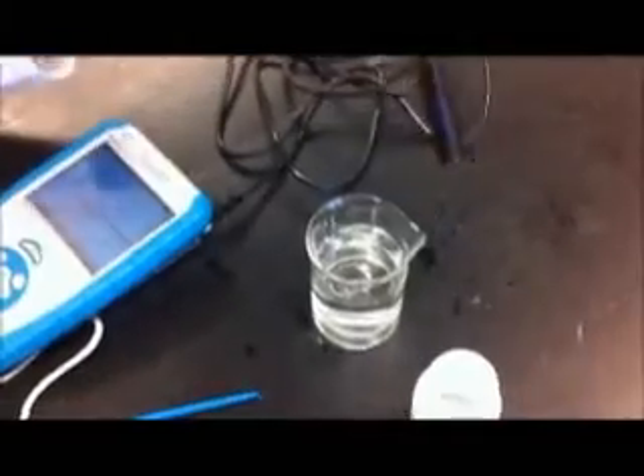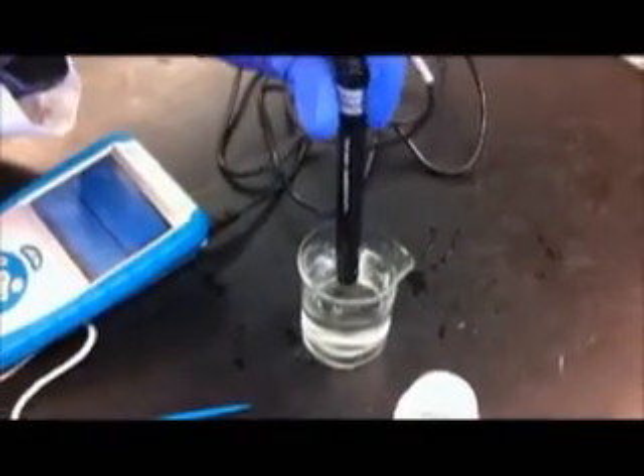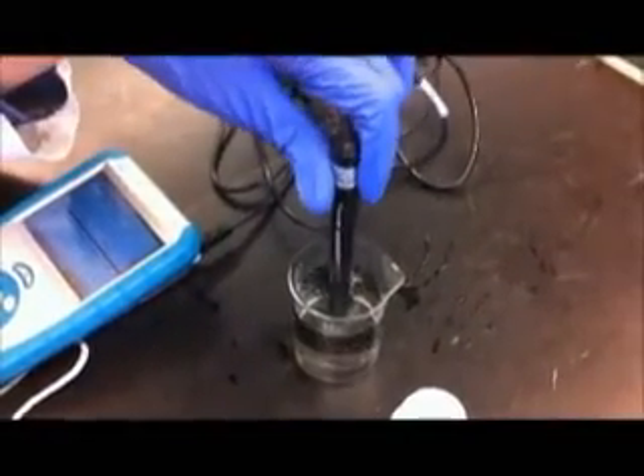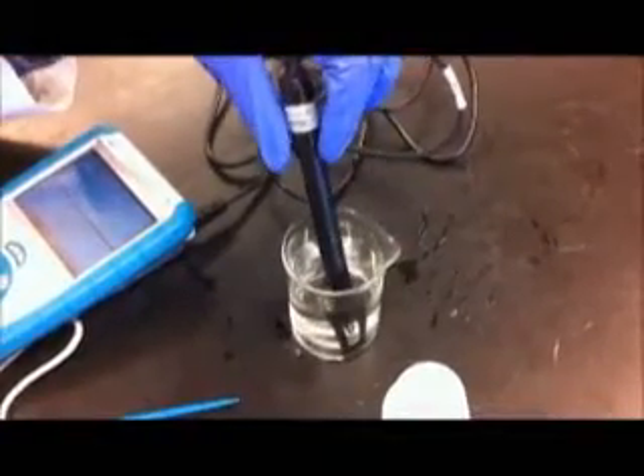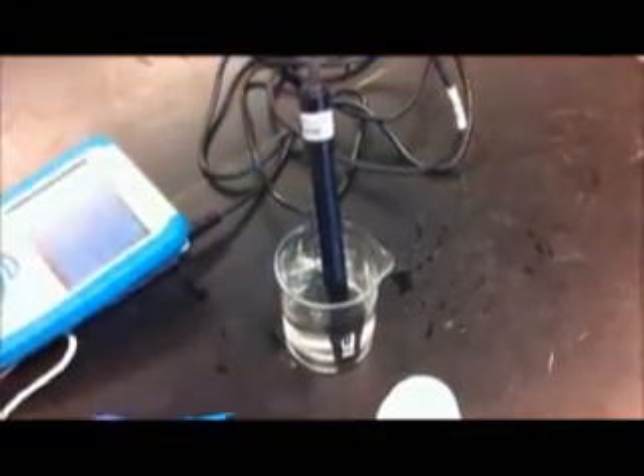Dip the Vernier conductivity probe into DI water. Be sure to submerge the entire electrode, but don't go too deep because the handle is not waterproof. Enter a value of 0 microsiemens. And select Keep.